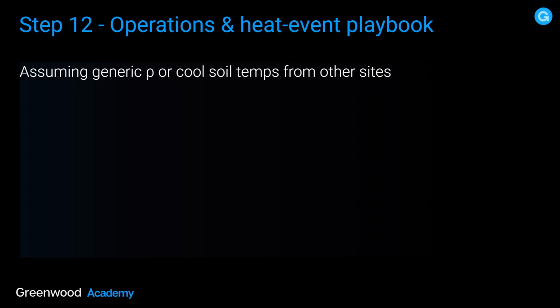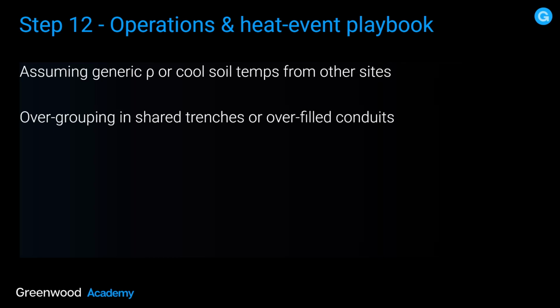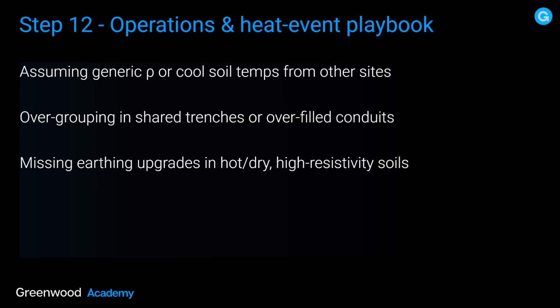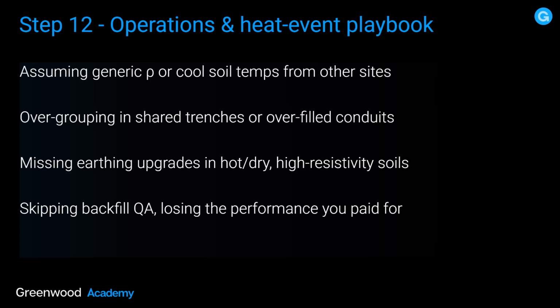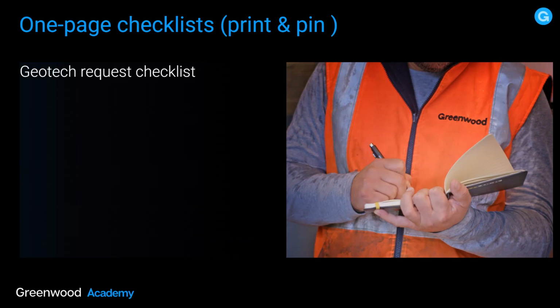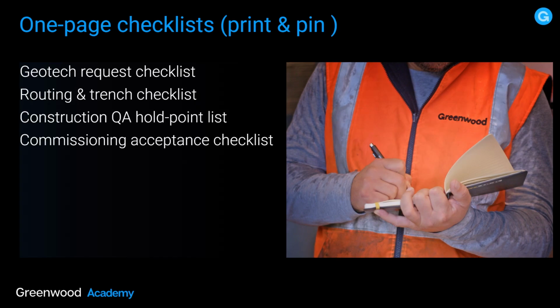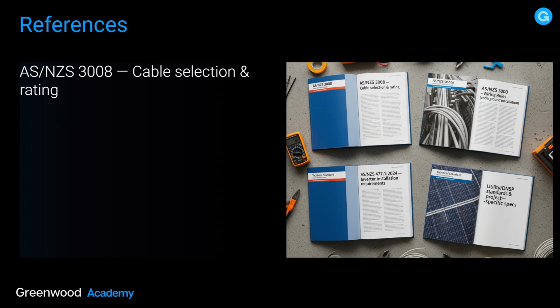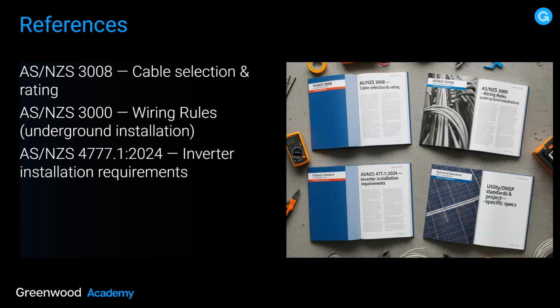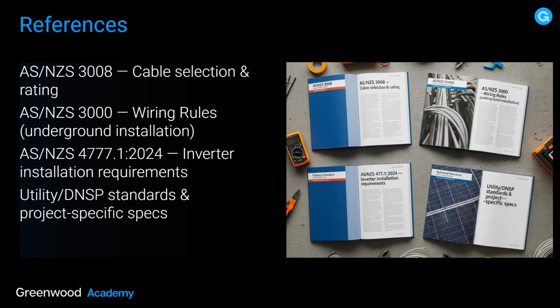Continuing on with step 12, we're assuming a generic thermal resistivity or cool soil temperatures from other sites. Yeah, but you know what they say about assumptions. Overgrouping in shared trenches or overfilled conduits, missing earthing upgrades in hot, dry, high resistivity soils, skipping backfill QA, losing the performance you paid for. One-page checklist, geotech request checklist, routing and trench checklist, construction QA hold point list, and commissioning and acceptance checklist. Now, your references obviously are AS/NZS 3008, AS/NZS 3000, and AS/NZS 4777.1 2024, and of course, utility and DNSP specific requirements. That's really important. Make sure you've got a good relationship with the DNSP.